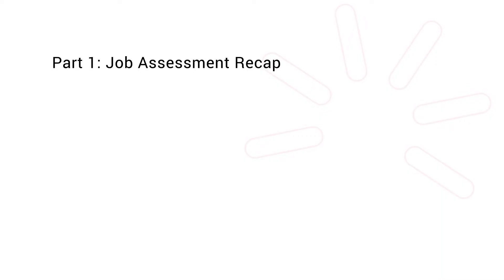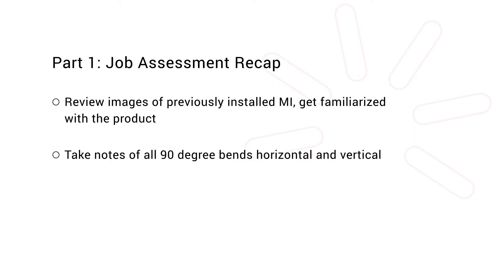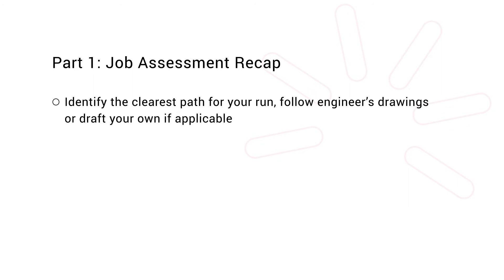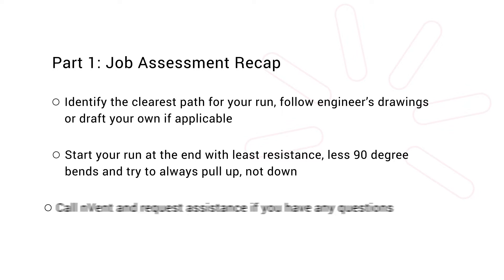Let's do a brief recap. Review images of previously installed MI and get familiarized with the product. Take notes of all 90 degree bends, horizontal and vertical. Account for the different gauges you'll be using and any enclosures, terminations, and bracings involved in the install. Identify the clearest path for your run. Follow engineer's drawings or draft your own if applicable. Start your run at the end with least resistance or fewer 90 degree bends, and try to always pull up, not down. Lastly, call nVent and request assistance if you have any questions.